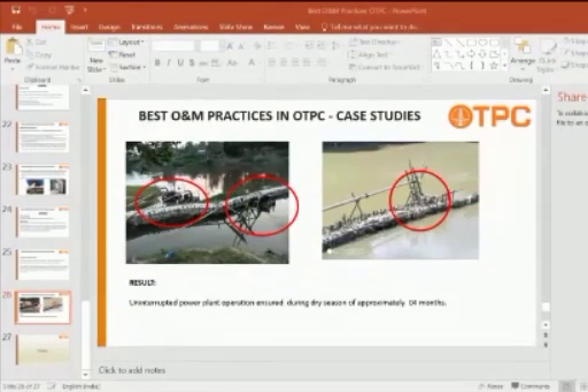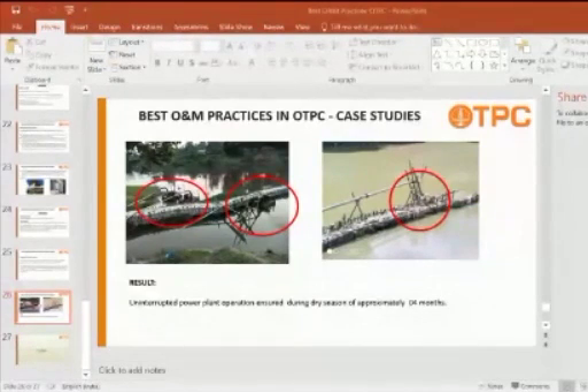So these were basically diesel engine driven pumps. From these pumps also we were supplying water to the river water intake system, and these were movable. They can be moved from the level where the water is low to the point where the level is adequate, by which method we could cater to the water requirement of the plant, and we could sustain the plant operation during the dry weather also.